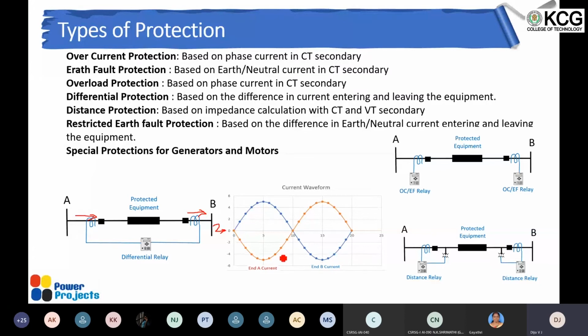That means this is an external fault, and the direction is just 180 degrees, because in power systems, when we talk about the protection part, the current going towards the protected equipment is considered positive. So that's how the connection is given to the relay. Here, the connection is given to the relay and the current goes through it in the other direction, so it's not towards the protected equipment, right? If it is going towards the protected equipment, that is positive. So it's 180 degrees out of phase. At any instant, if you calculate the sum IA plus IB, it's 0. That's the idea of differential protection.